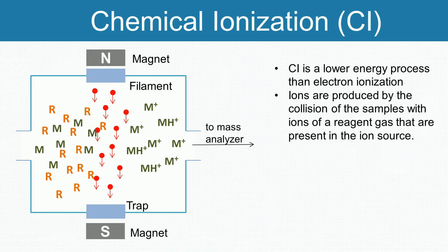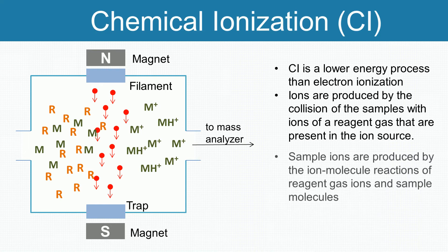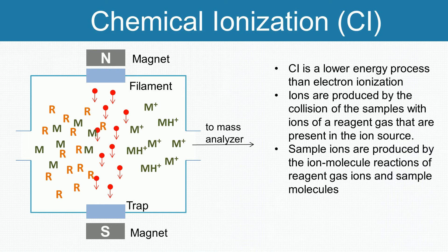Inside the ion source, the reagent gas is extremely more than samples. Reagent gas is first subjected to electron impact to produce reagent gas ions by the fast electrons from the filament. Sample ions are produced by the ion-molecule reactions of reagent gas ions and sample molecules.